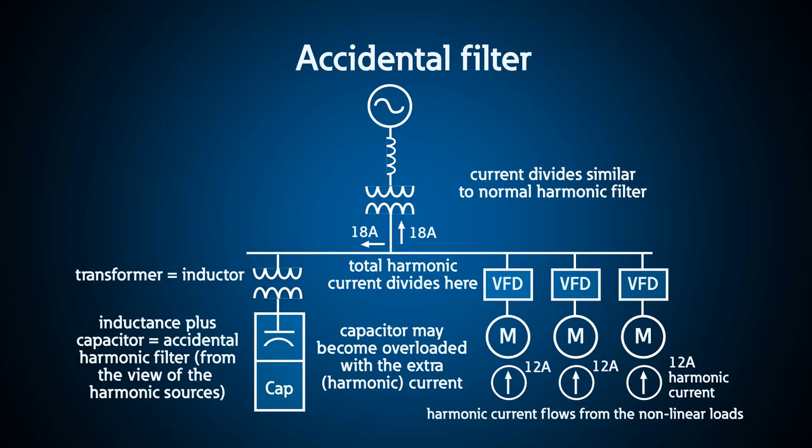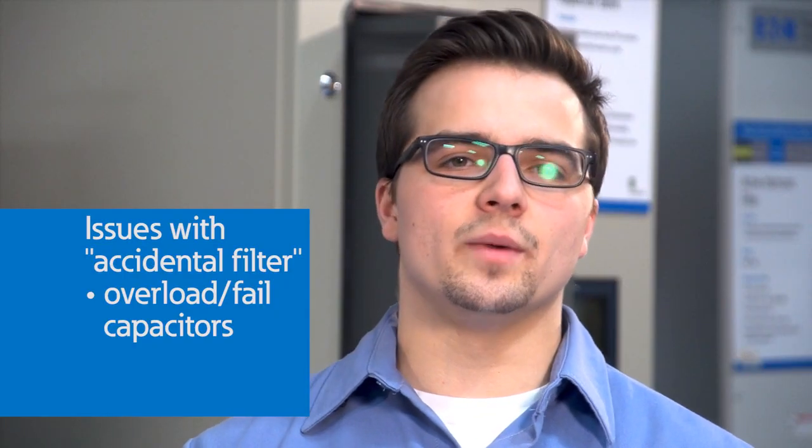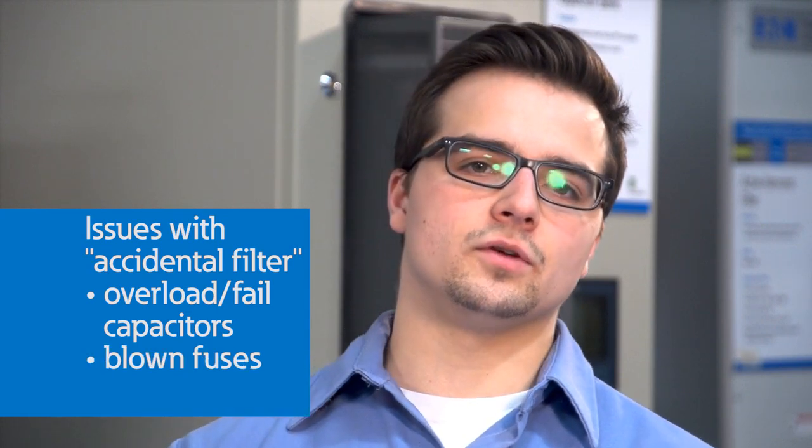When this occurs accidentally — for example, when a transformer and capacitor are in series from the point of view of a harmonic source — we might call this an accidental filter, because you could draw harmonic current into the capacitor from other harmonic loads on the power system. When this occurs, you may overload the capacitor and often blow fuses or trip the breaker feeding the capacitor, so you should take care to understand what might happen any time you apply capacitors.